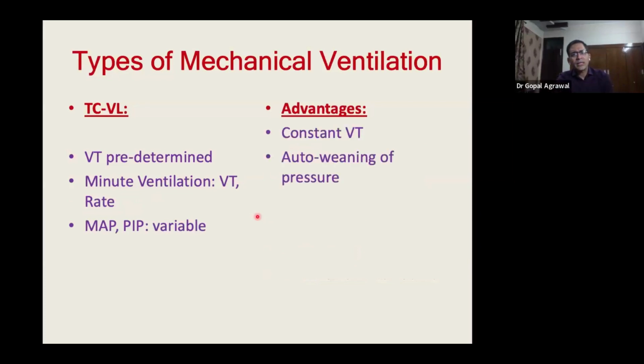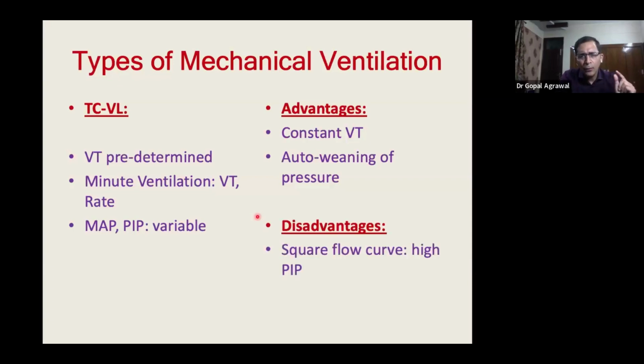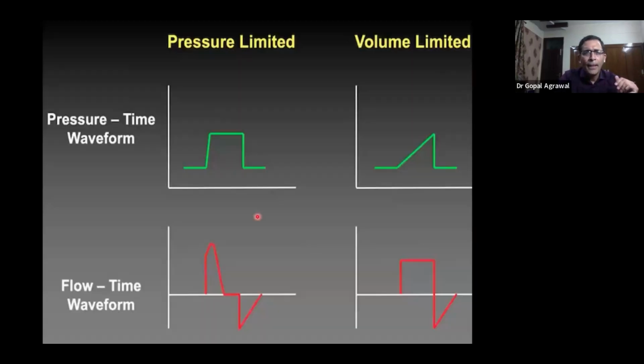Advantages of volume ventilation: with the volume limit, a constant tidal volume is being delivered, and there's auto-weaning of pressure. We'll see that in later slides. The disadvantage is that the flow curve is a square wave, for which increased PIP is required to deliver a certain volume. So let's see this waveform.